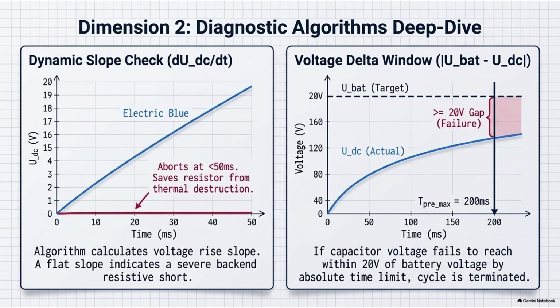It cannot afford to. If there is a massive downstream short circuit, a giant hole in our pool, the voltage curve will not rise. The slope will remain completely flat or near zero. Okay. If the software calculates a flat slope at the 50 millisecond mark, it deduces instantly that a severe leak exists. It proactively aborts the pre-charge sequence right then and there. It's like turning on the hose, looking at the pool for one single second, seeing the water pouring out a drain, and immediately shutting off the valve rather than standing there for an hour hoping it magically fills up.